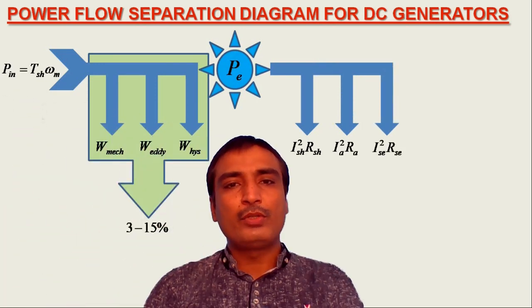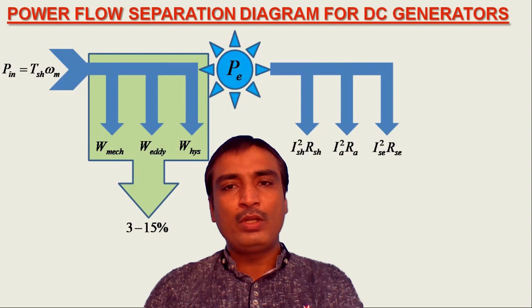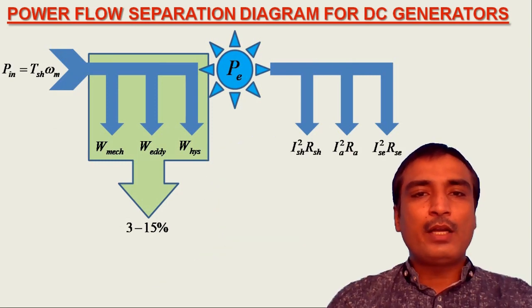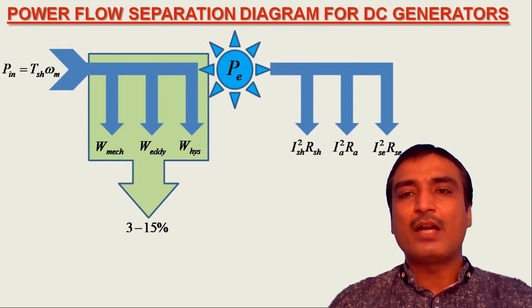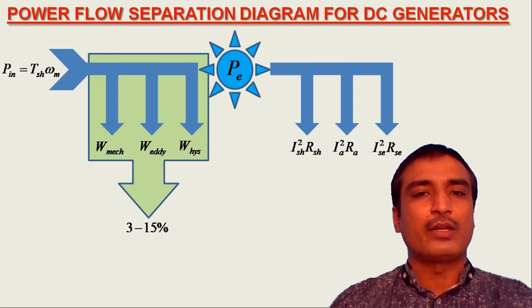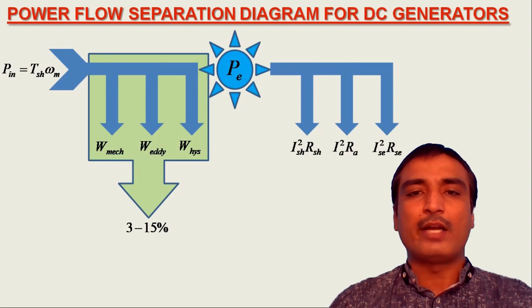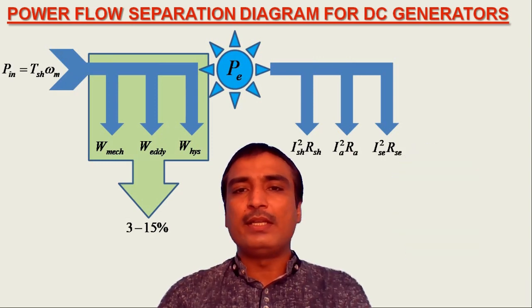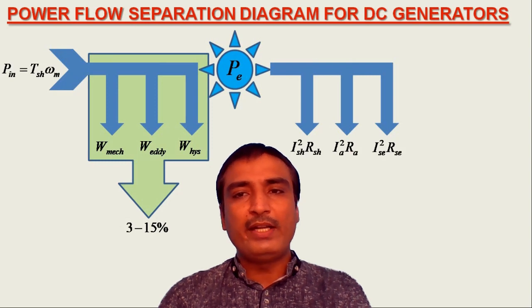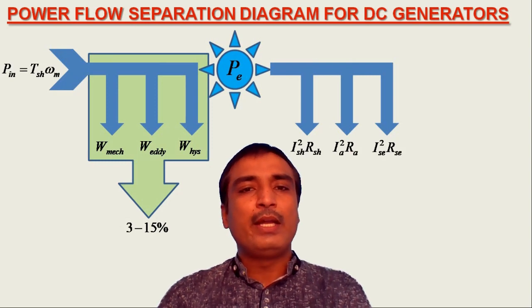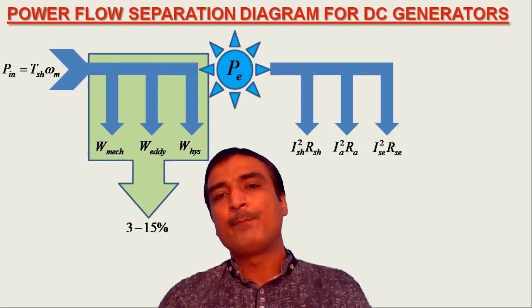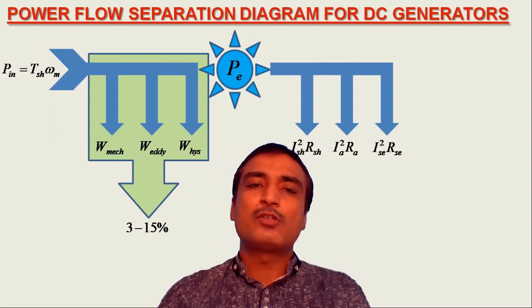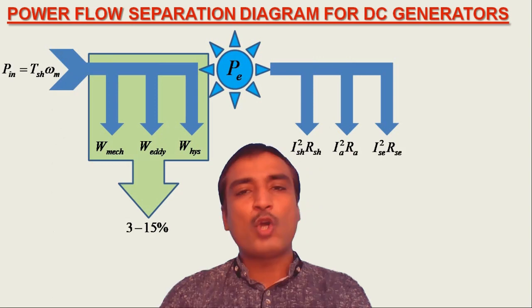One may ask about the copper losses in interpole and compensating windings of the DC generator. The interpole and compensating windings are connected in series with the armature and thus carry full armature current. So the copper losses in interpole and compensating windings must be included in the armature circuit copper losses. Likewise, power losses due to brushes may also be added in the armature circuit copper losses.